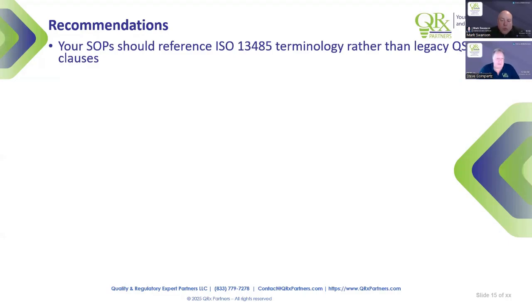You should be doing this anyway because the QMSR is coming out, where you're creating SOPs related to computer software assurance. Leverage the ISO 13485 terminology rather than your legacy 820 clauses, because you'll end up having to change them anyway. And they're already telling you, look, we're adopting these concepts in preparation for this anyway.